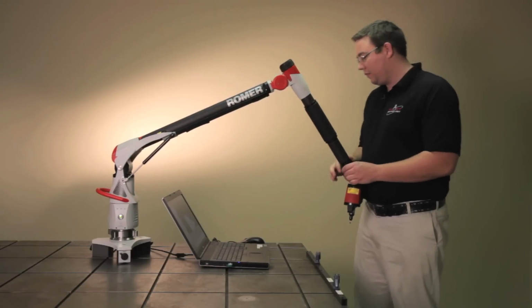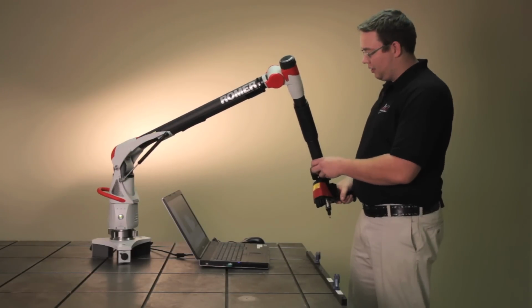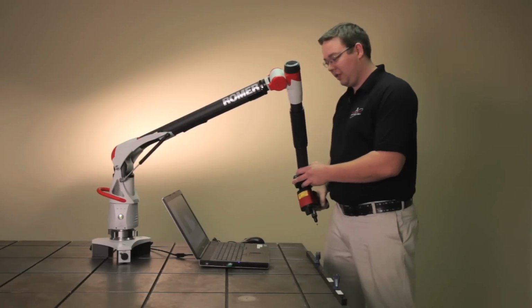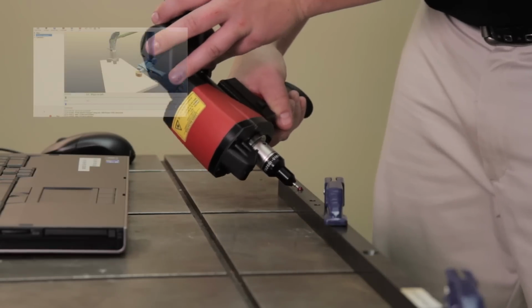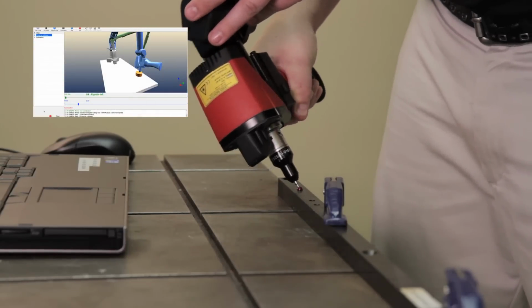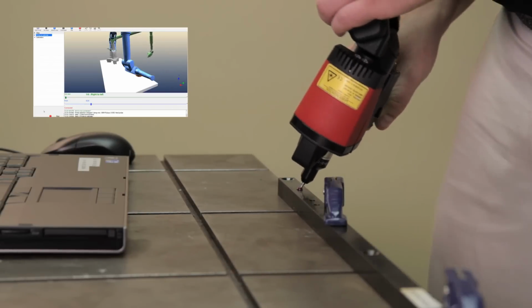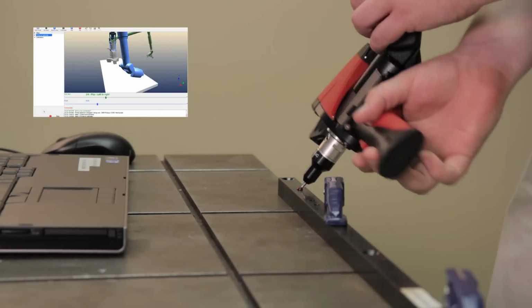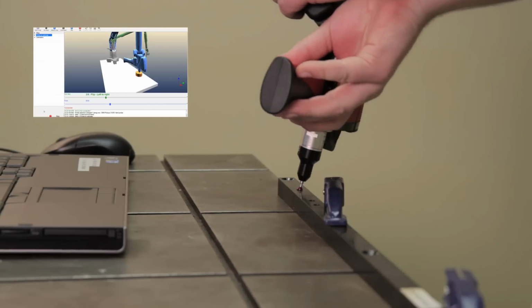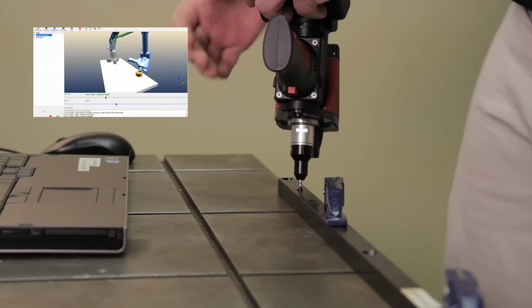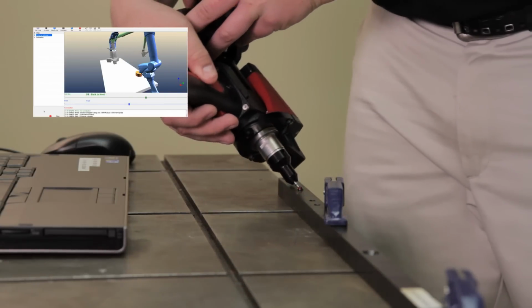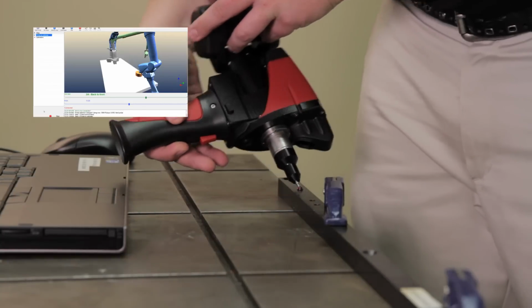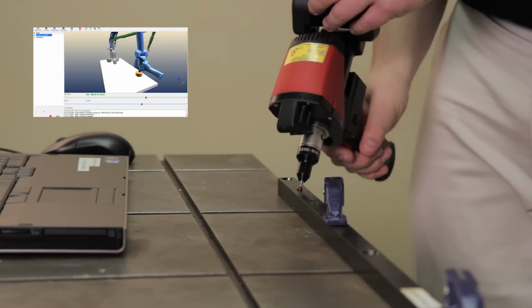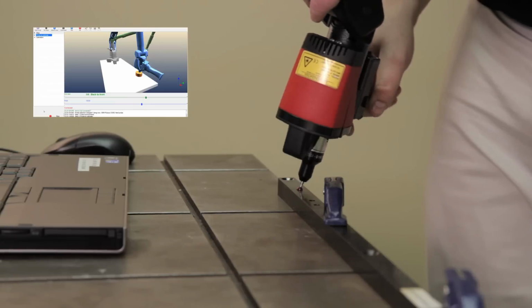Grab the arm and mimic what they show you on the screen. You will need to take a total of 20 points. The purpose of all the different ways is to exercise all the encoders.